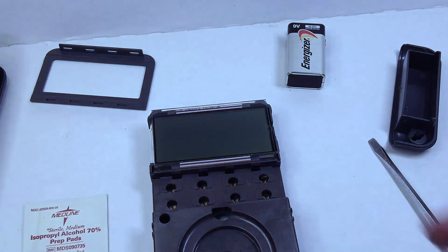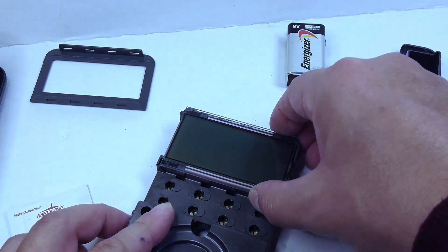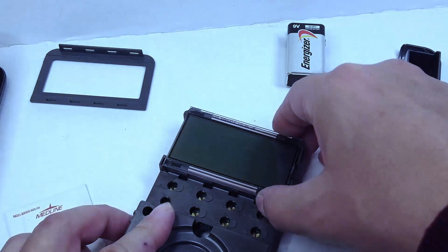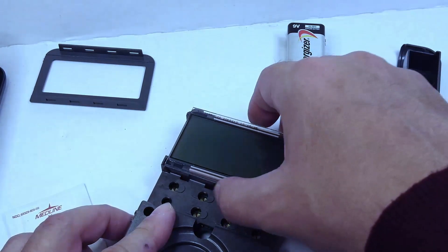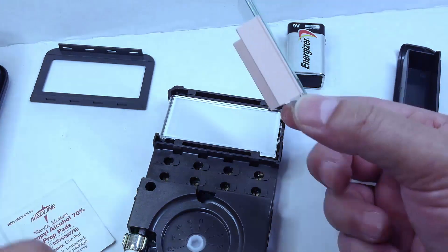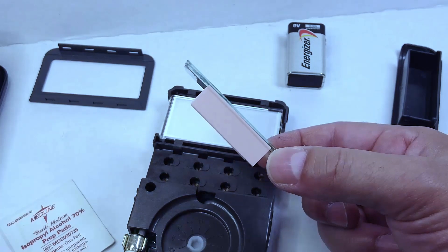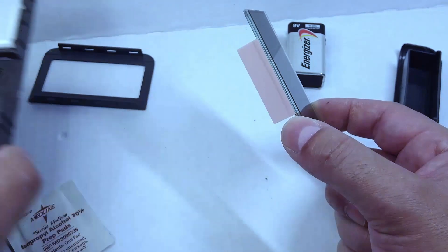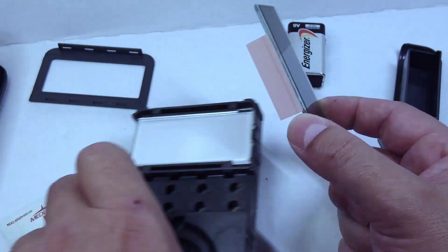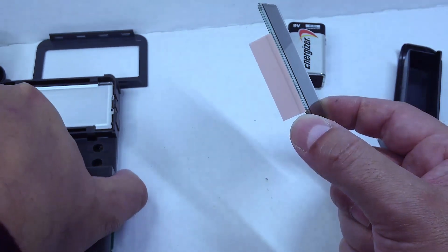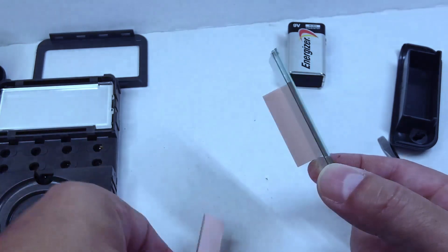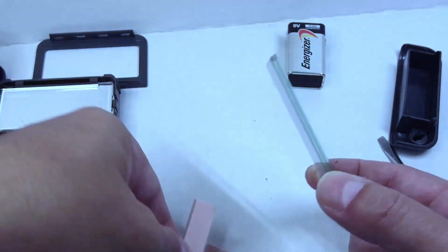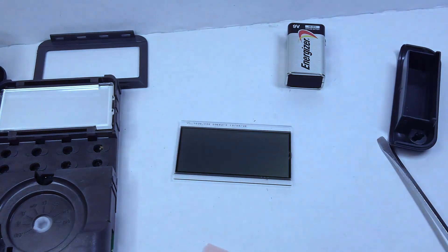So I'm going to gently lift up on the glass. And here we go, as expected, we have the elastomeric connectors that are stuck to the glass. That's perfectly normal. I'm going to set this over here to the side for now. We're going to remove the pink elastomeric connectors from the glass. They're just stuck on there—it's okay, it's not going to cause any harm to pull them off.